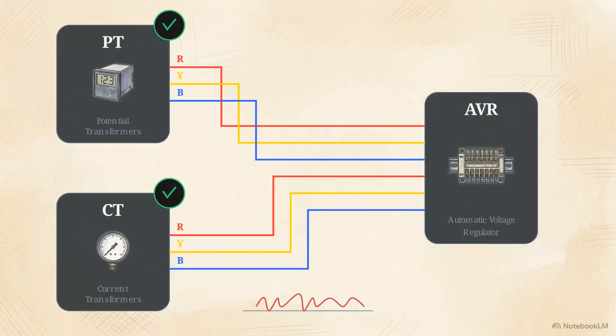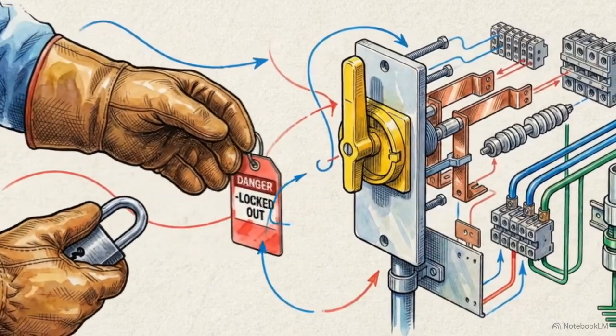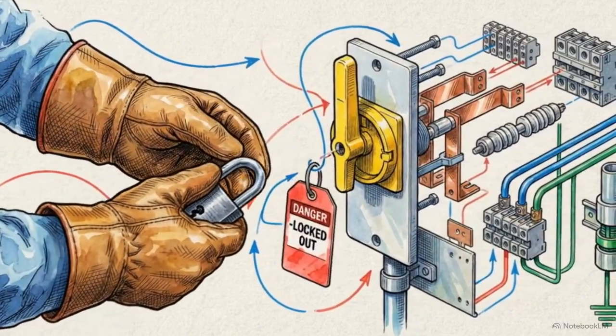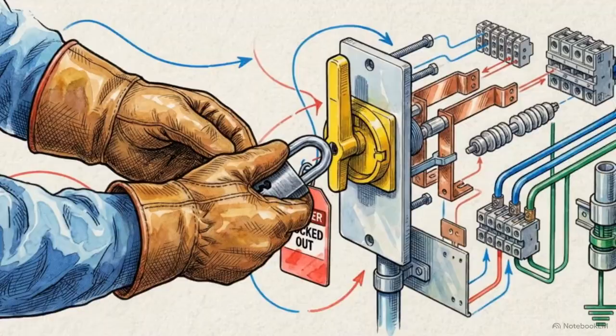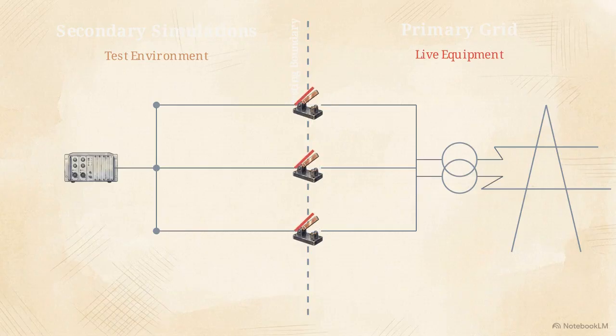to the AVR. Finally, enforce the mandatory lockout-tagout, carefully executing a strict 5-step safety isolation protocol before making any live equipment connections. Establishing this boundary ensures that secondary simulations remain isolated from the primary system, preventing unintended control commands or backfeeding during the test sequence.